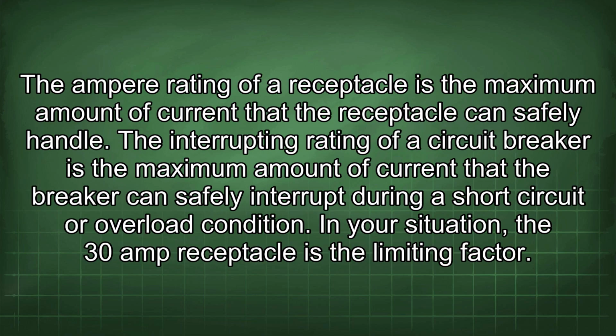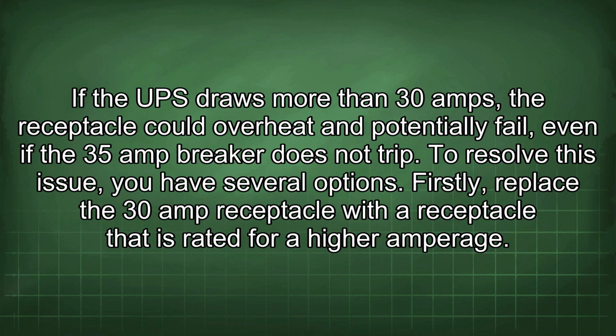The ampere rating of a receptacle is the maximum amount of current that the receptacle can safely handle. The interrupting rating of a circuit breaker is the maximum amount of current that the breaker can safely interrupt during a short circuit or overload condition. In your situation, the 30 amp receptacle is the limiting factor. If the UPS draws more than 30 amps, the receptacle could overheat and potentially fail, even if the 35 amp breaker does not trip. To resolve this issue, you have several options.